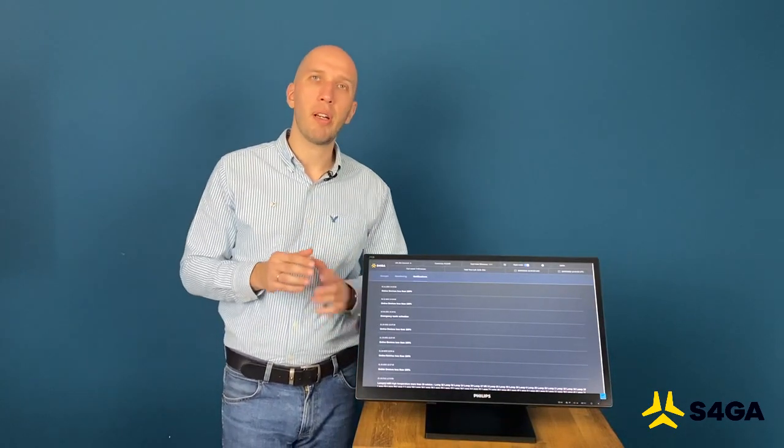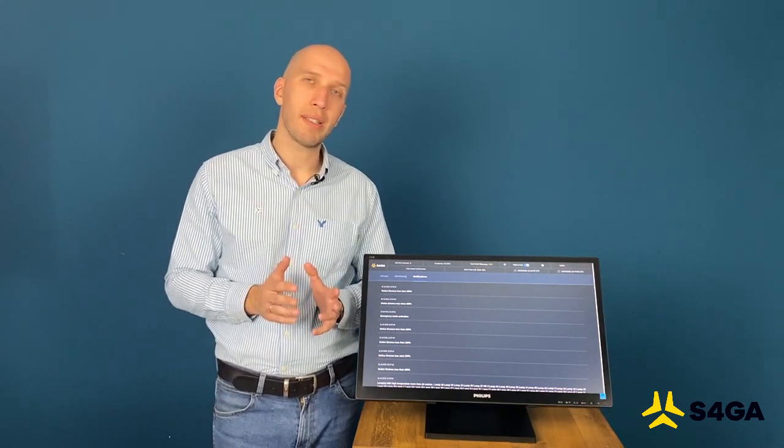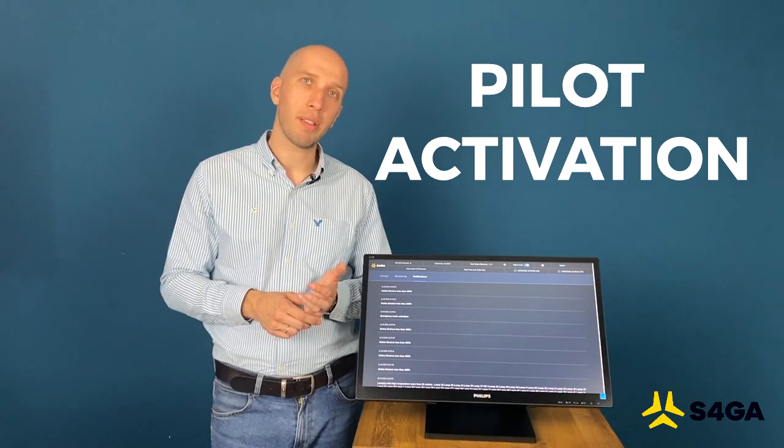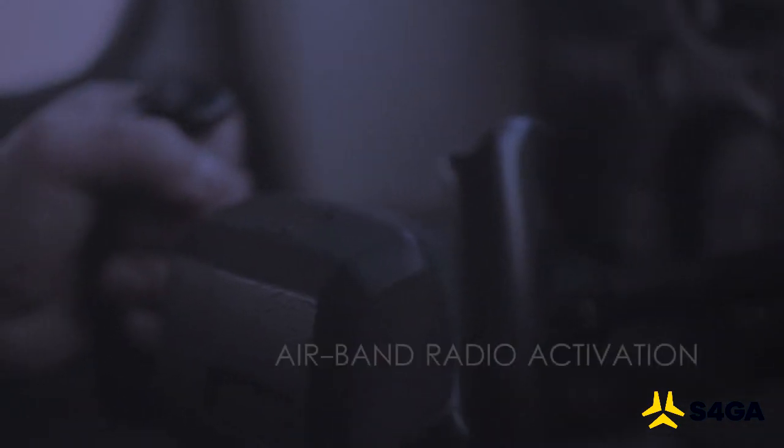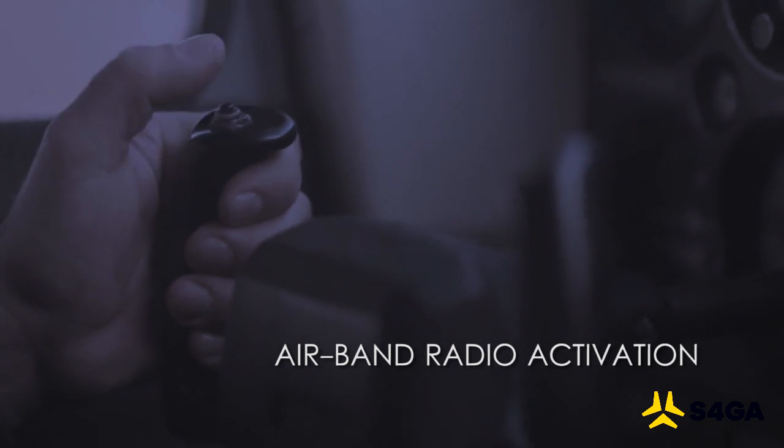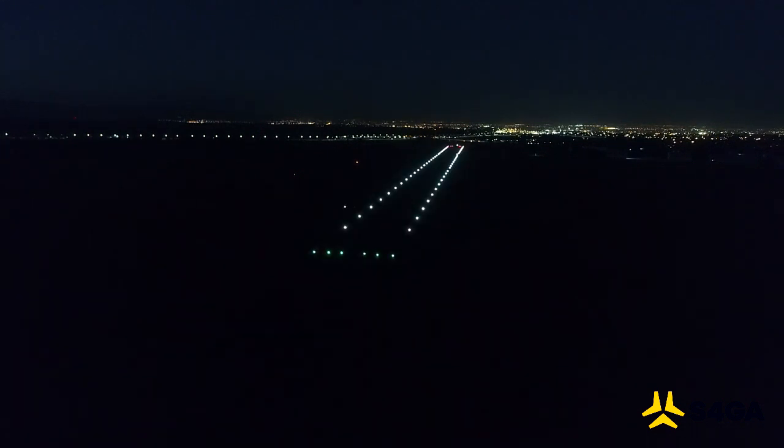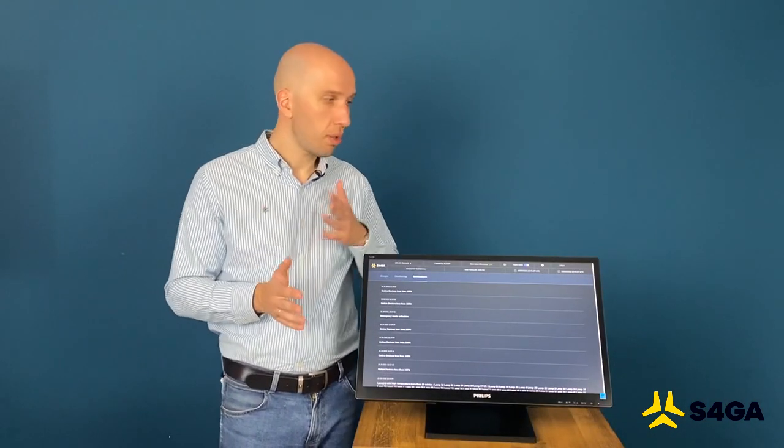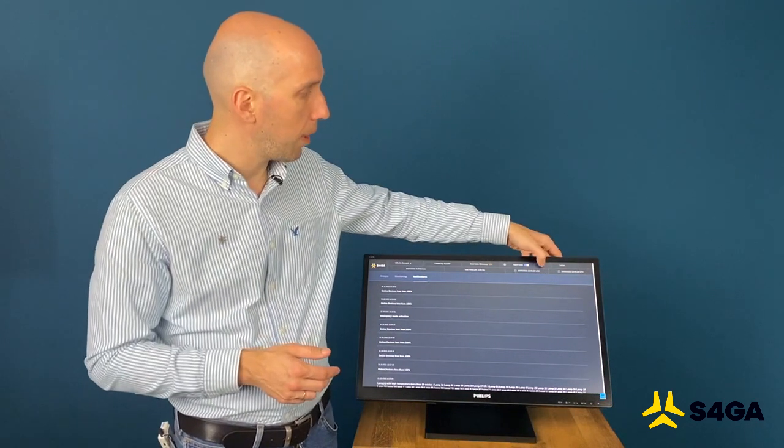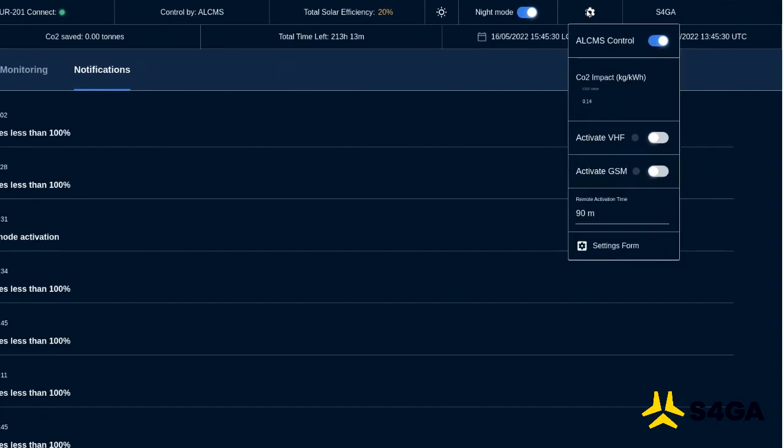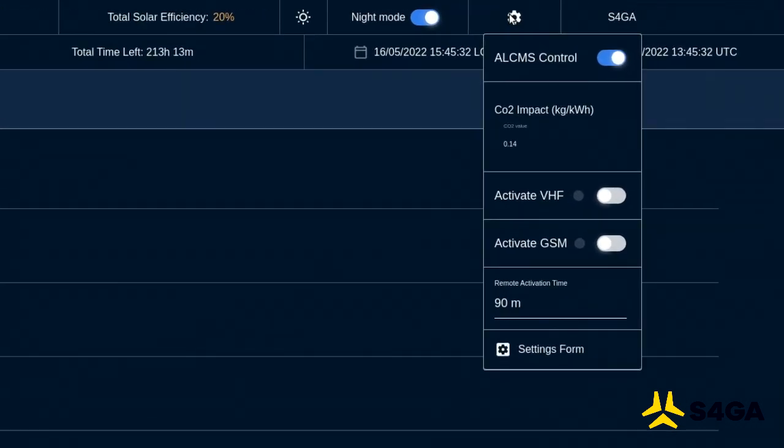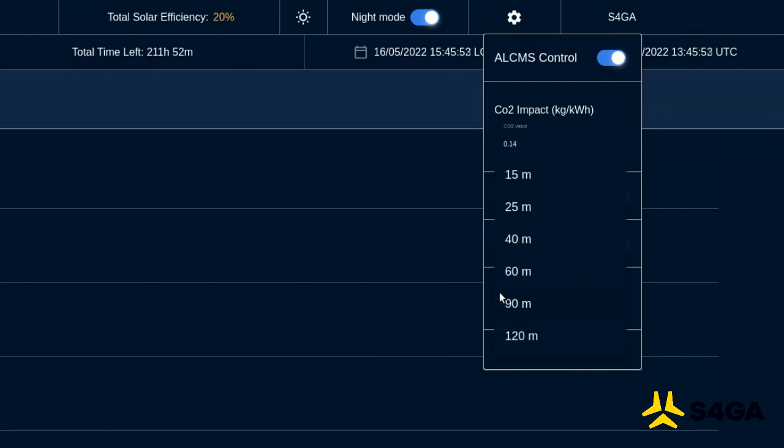S4GA remote control system allows for remote activation of lights via pilot activation or GSM-based activation. What does it mean? It means that pilot arriving to the airport where there is no air traffic control can activate the lights with the help of push to talk button by pressing three, five or seven times. And anybody with a registered phone number can activate lights change intensity with the help of regular cell phone. Now, in order to deactivate or activate those functions, we have this part available in ALCMS. We go to setup, as you can see right here, you have activate VHF, so it's a pilot activation and activate GSM. And both types of remote activation are linked to timer. So when we activate anything remotely, then it is activated as long as it is defined in a timer. And timer can be set up from 15 minutes to 120 minutes.